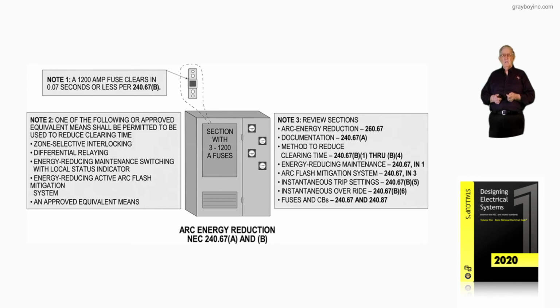Now, the energy reducing maintenance capability is 240.67 informational note 1. So we could read up on that or go to the annex, I believe it's O, to NFPA 70E and read a lot more information on this. Or go to the manufacturer. Go online and get the UL document that gives you information. Now, the arc flash mitigation system is 240.67 informational note 3. And it's going to reduce the energy big time.